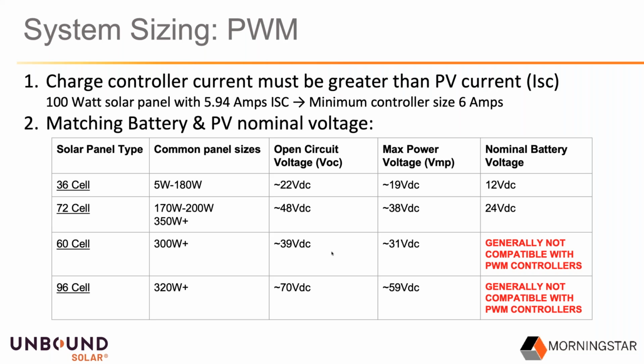So basically, if we're going to charge at 32 volts, the 60 cell panel isn't going to be high enough, especially since heat lowers your voltage. If you have voltage drop, that could be 1 or 2% right there easily. So the 60 cell panel in most cases would not be high enough voltage to charge a 24 volt battery, and that's why we have to go to the 72 cell. Hopefully that helps address the question or at least shed some light on the panel types. Yep, I think that clears things up.